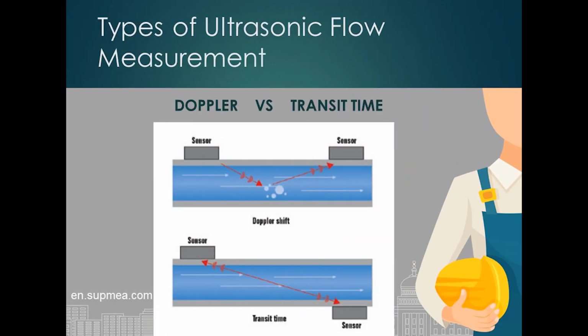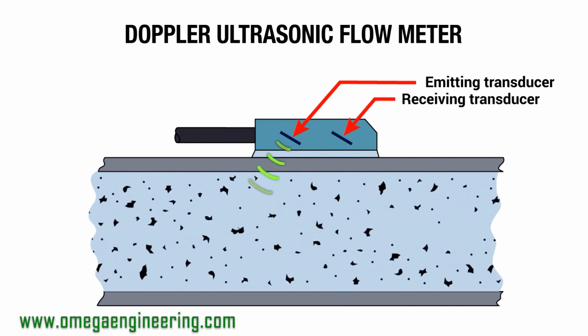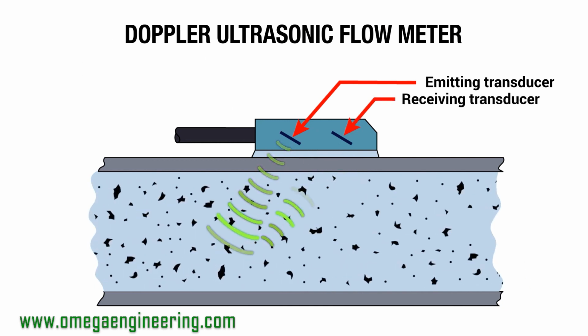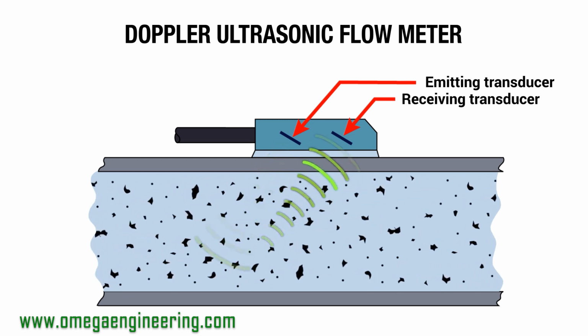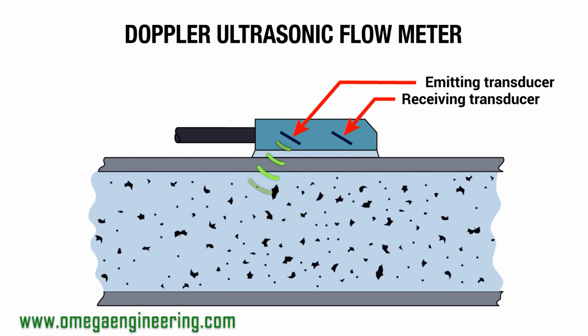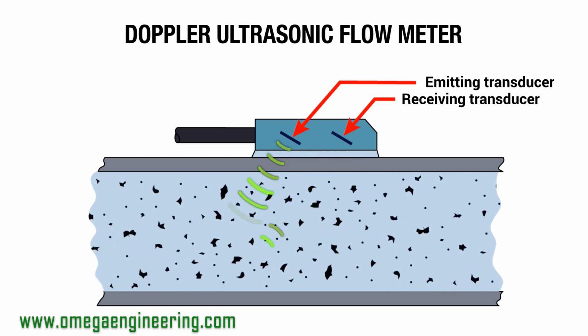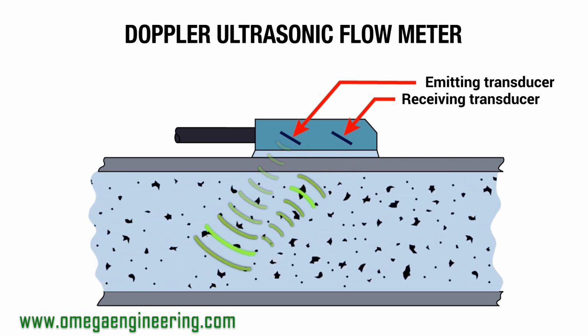There are two types of ultrasonic flow meters in use today, and they operate on two different engineering principles: Doppler and transit time. The Doppler ultrasonic flow meter operates on the principle of the Doppler effect, using a transducer to emit an ultrasonic beam into the stream flowing through the pipe, and tracking the frequency shift in the sound waves emitted by a moving source.